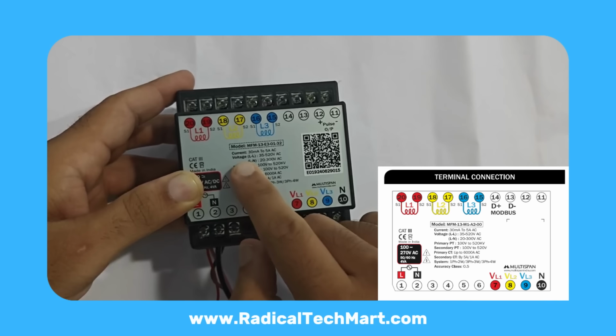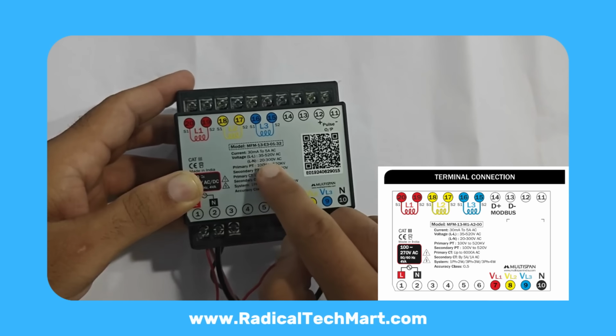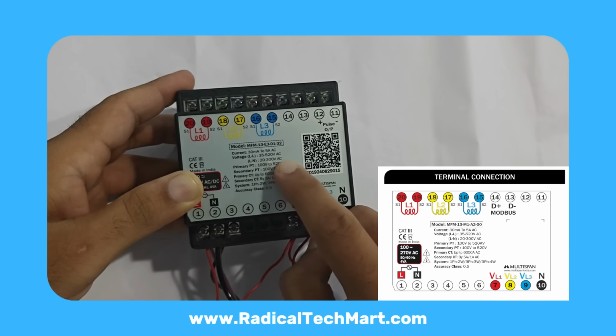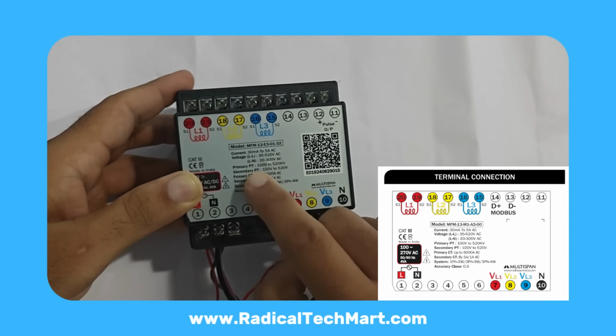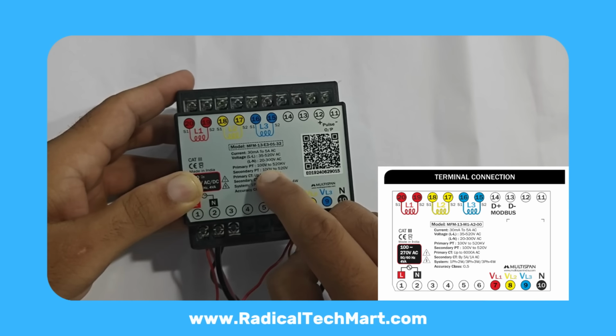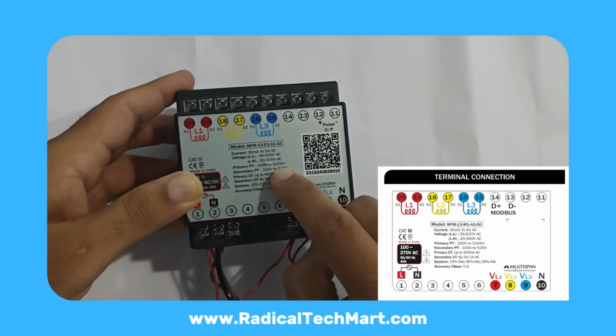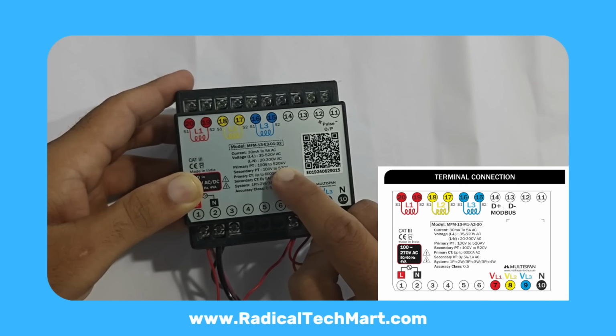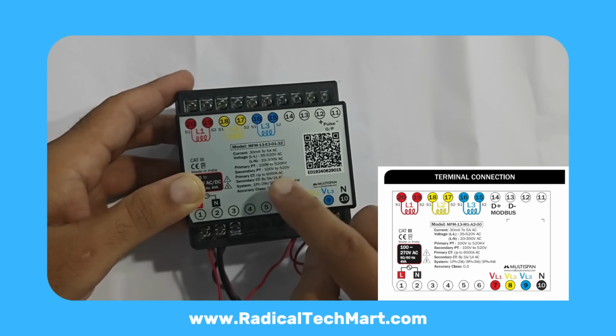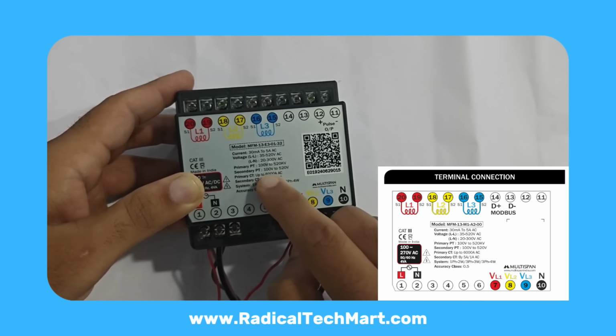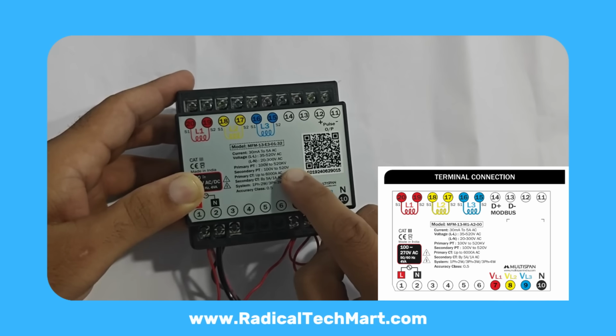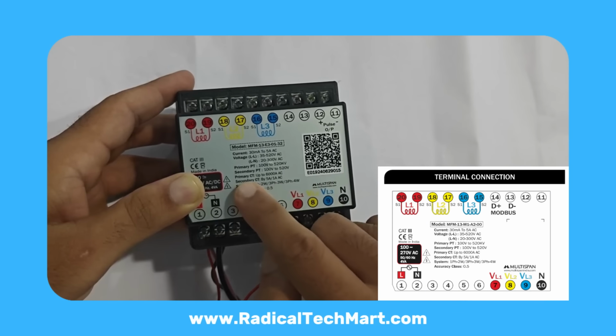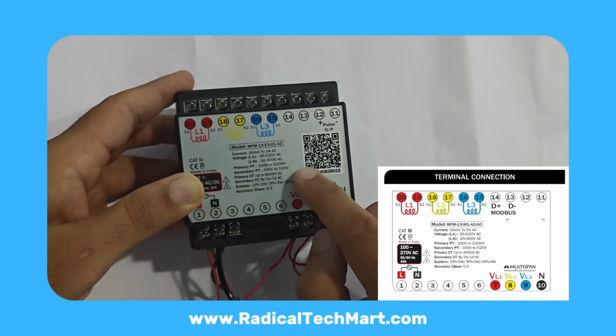Now let's talk about measurement ranges. Line voltage range, 35 volts to 520 volts AC. Line neutral voltage range, 20 volts to 300 volts AC. PT, potential transformer, ratios. PT primary, adjustable from 100 volts up to 520 kilovolts. PT secondary, 100 volts to 520 volts.